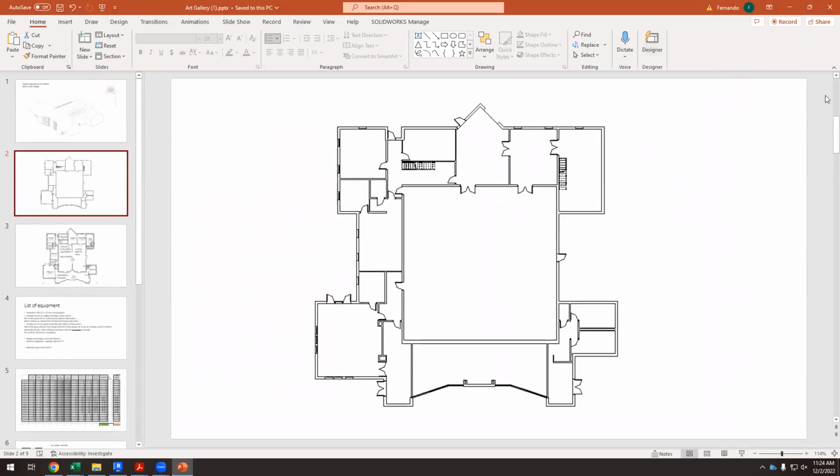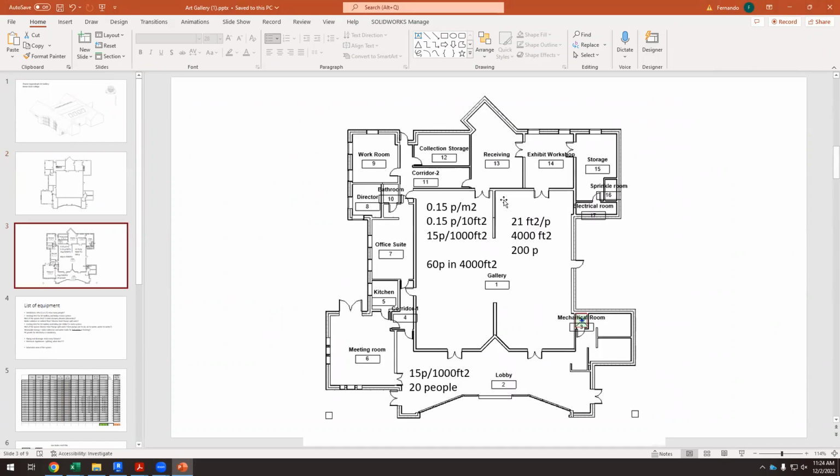Because this is the Excel file, now you have to work with Revit. And so we have to come up with an idea. I think in this building, the art gallery can be divided into two different spaces. So if this is divided into two different spaces, I can have supply diffusers here and return diffusers there. Because if I close this partition, in one of the spaces I will have supply, and in the other I will have return, and it won't work.